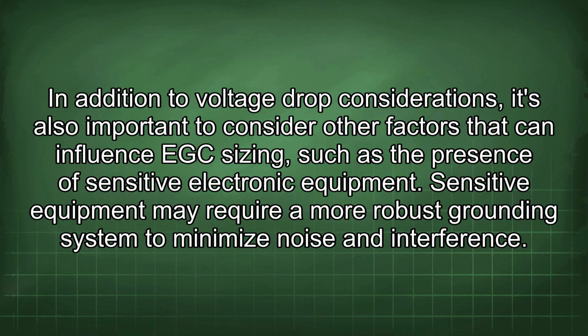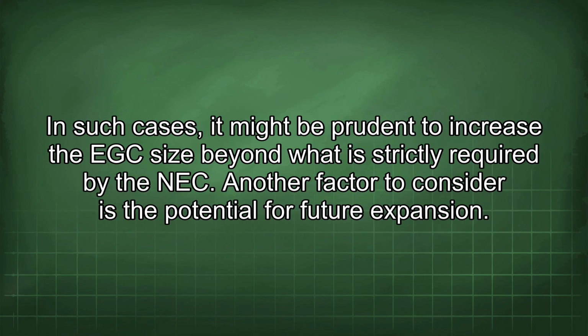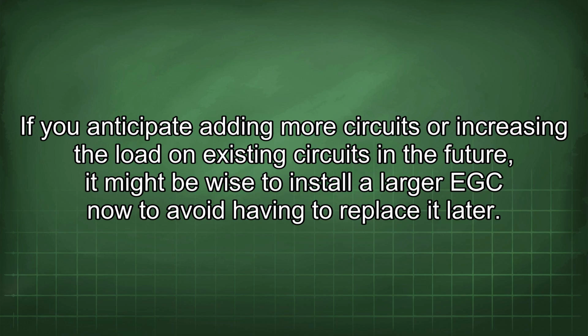In addition to voltage drop considerations, it's also important to consider other factors that can influence EGC sizing, such as the presence of sensitive electronic equipment. Sensitive equipment may require a more robust grounding system to minimize noise and interference. In such cases, it might be prudent to increase the EGC size beyond what is strictly required by the NEC. Another factor to consider is the potential for future expansion. If you anticipate adding more circuits or increasing the load on existing circuits in the future, it might be wise to install a larger EGC now to avoid having to replace it later.